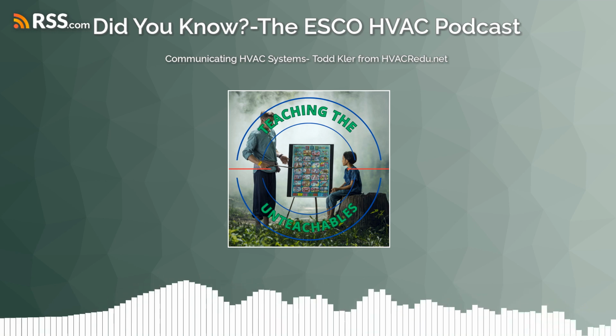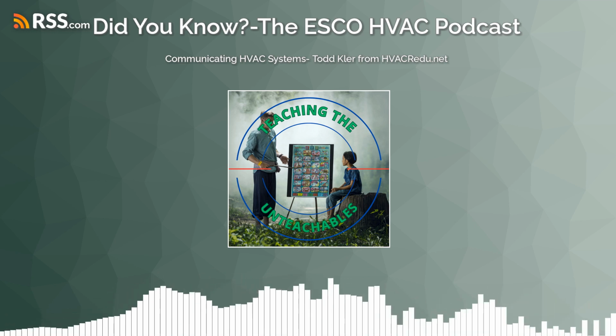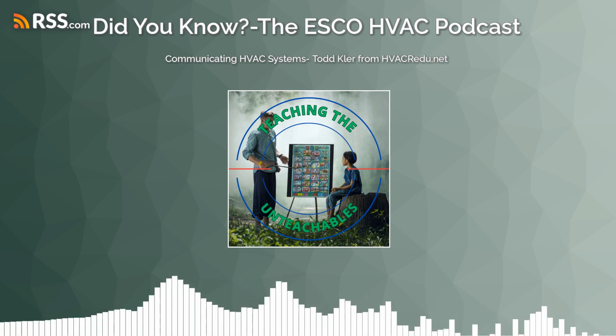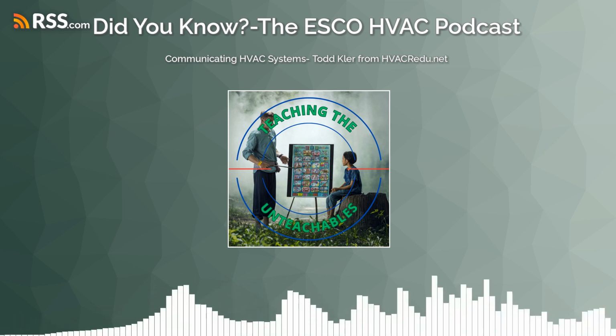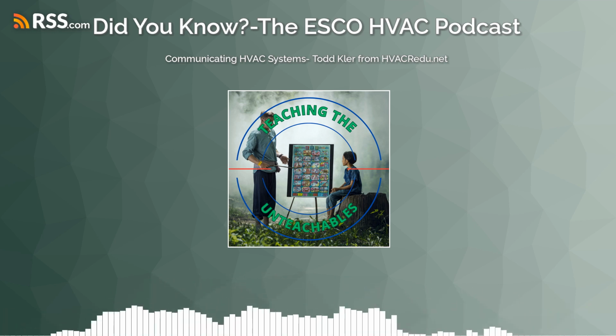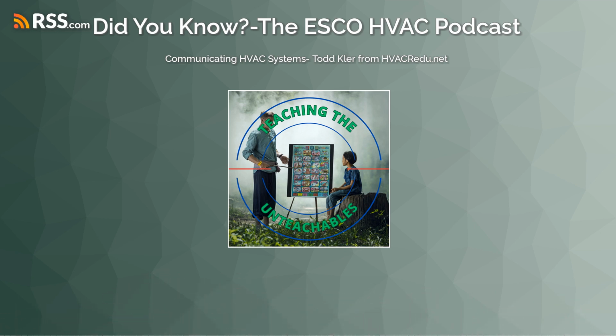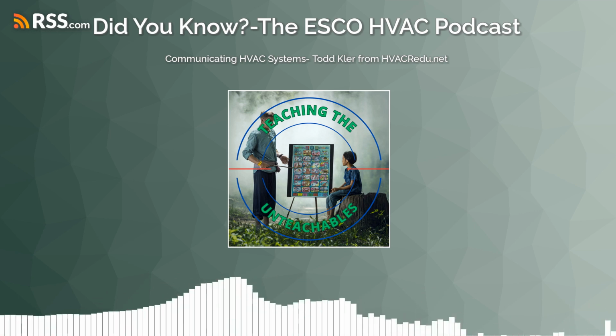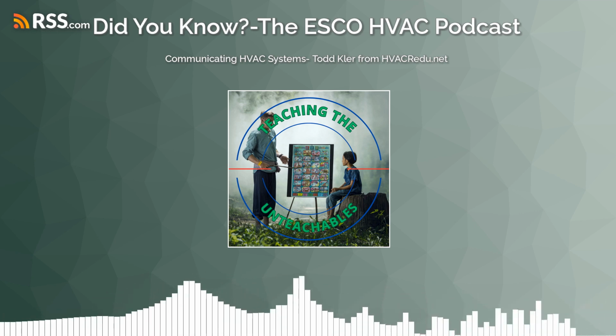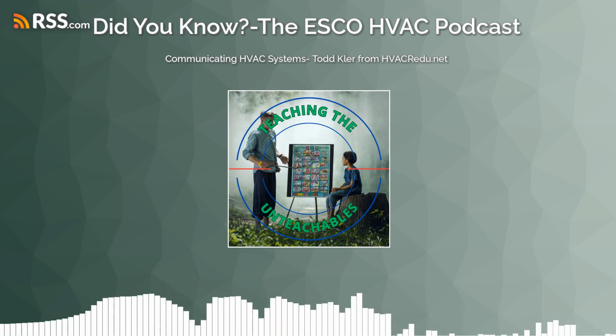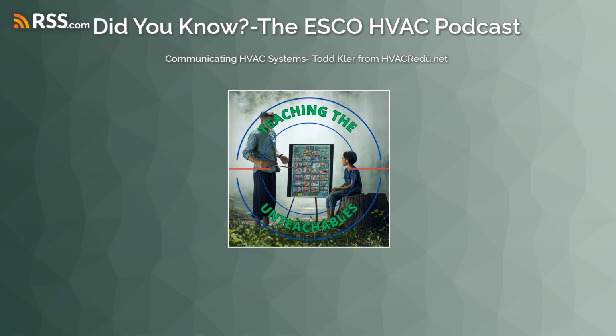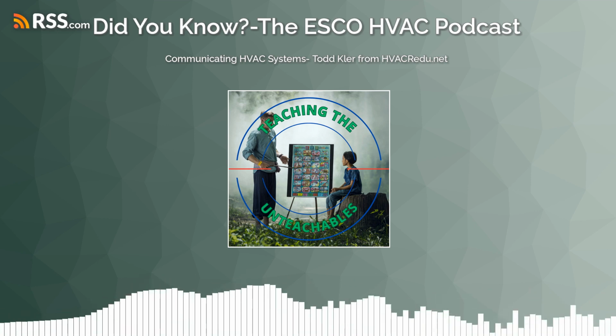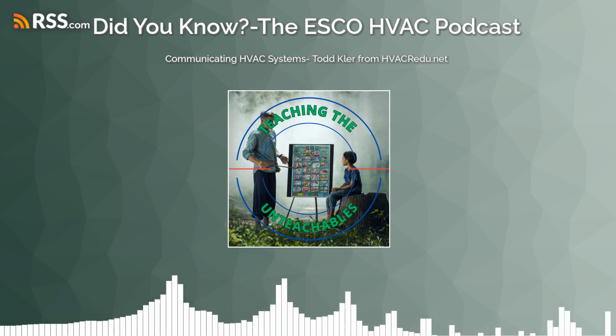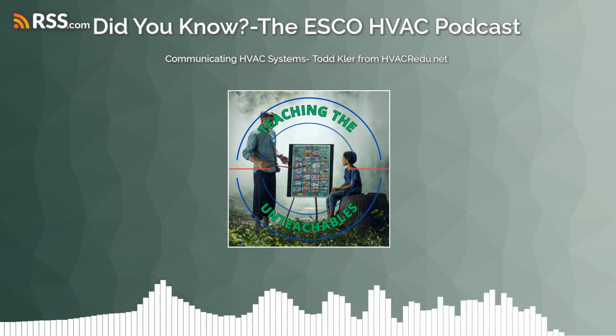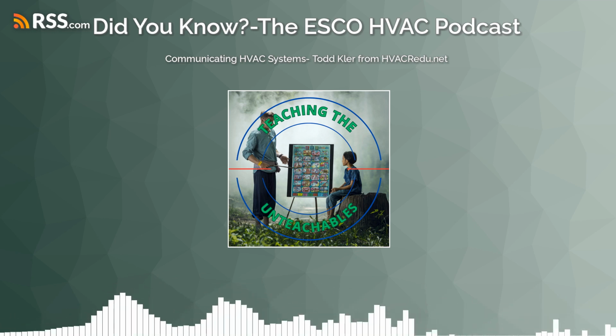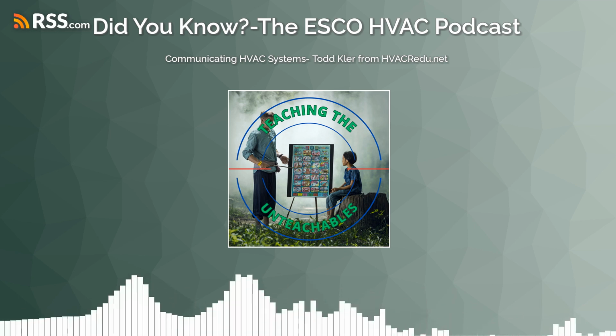Now, we're not going to go this deep on it. We're not going to bring in an oscilloscope, although maybe down the road we'll do this so we can actually talk about it a little bit. If we were to put an oscilloscope on a communicating network, we're going to see our ones and zeros, but we're also going to see those as a positive reference to ground and as a negative reference to ground. We're going to go both directions because they came from our AC sine wave. So the important thing to remember is all of these DC communicating voltages started with our 24 volt AC power supply. So where do our DC circuits begin? Typically, it starts at our indoor unit. For residential unitary split systems, it starts at our furnace or our air handler, where our original power supply was. So we'll take that AC voltage, turn it into the DC voltage, and then start pulsing that.